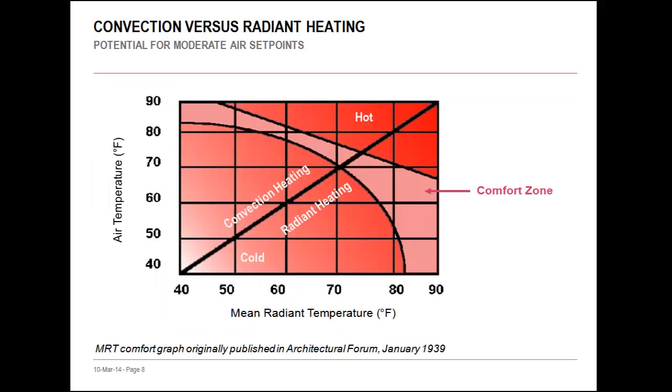By integrating radiant, we also impact the occupant's experience of thermal comfort, allowing us to design with more moderate air set point temperatures. This graph shows air temperature — what we see on a thermostat — on the y-axis, and mean radiant temperature, the average temperature of all the surfaces in the space, on the x-axis. The pink band is an approximate comfort zone. When incorporating radiant cooling, we are directly altering the mean radiant temperature, shifting us to the left on the graph. To stay within the comfort zone, we can elevate the air temperature — instead of a typical set point of 72 or even 70°F, we can set air temperature at 75 to 78°F. Likewise, as we increase the mean radiant temperature through the warmed slab, we can decrease the air temperature to about 68°F.